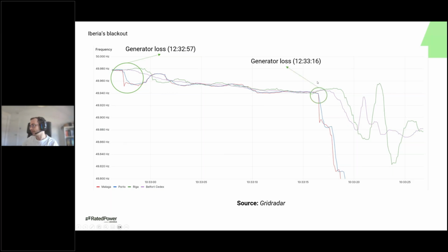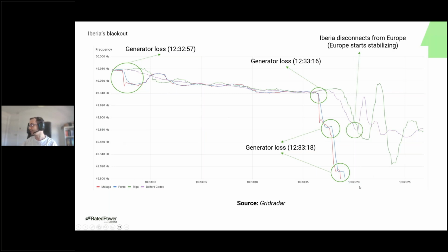However, around 20 seconds later, we had another generator loss, and this led to a cascading effect of losing even more generators, frequency dropping more and more, and it went down to, according to ENTSO-E, 48 hertz. Then another interesting thing that happened: you see here that in Malaga and Porto, both in Iberia, frequency dropped really low. However, in Riga and Belfort, despite having a drop, it didn't go as bad. This is because at 10:33 and 20 seconds, Iberia disconnected from Europe. So Europe started stabilizing, and Iberia just went even worse.